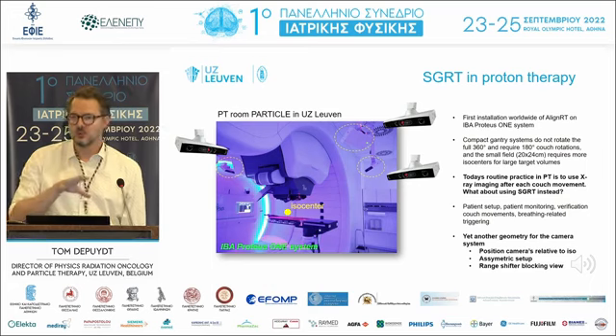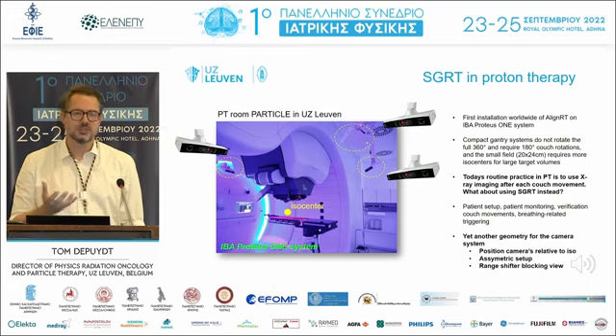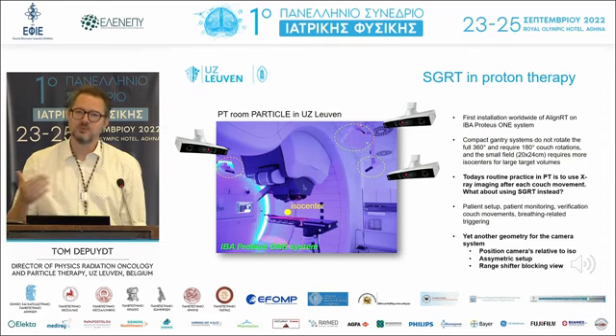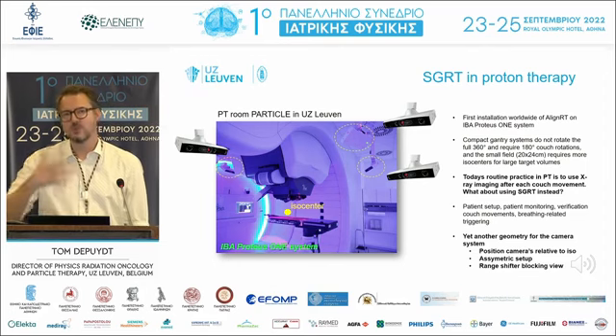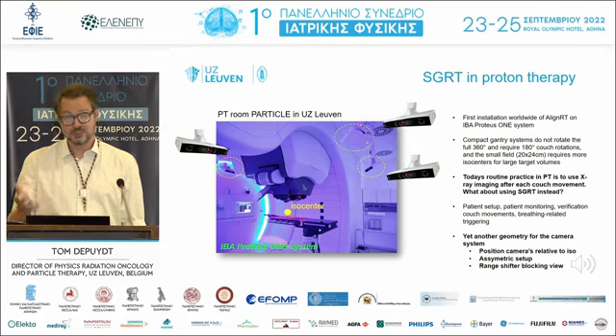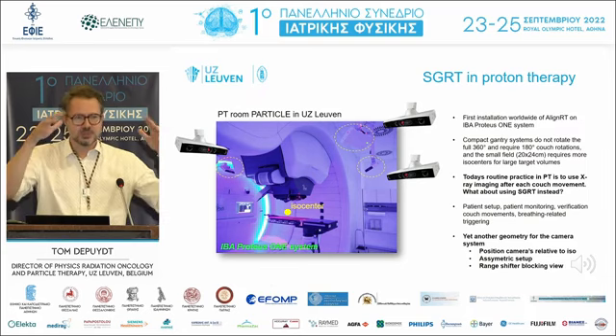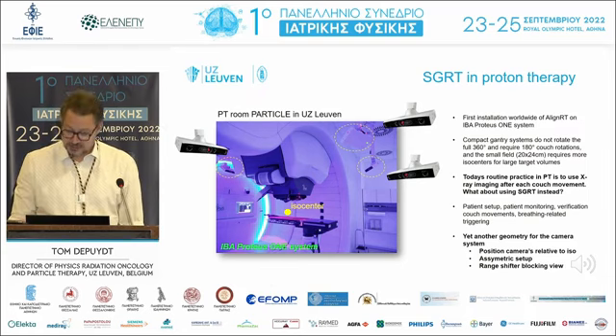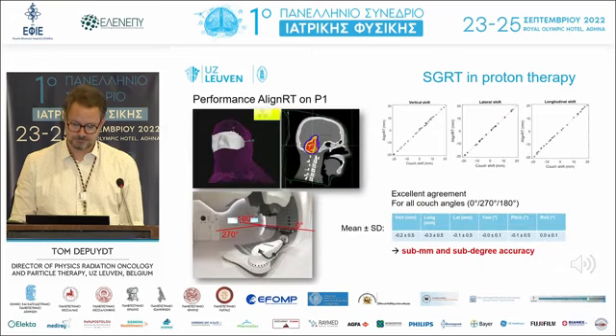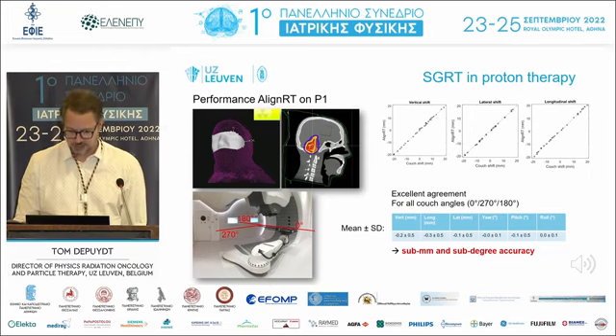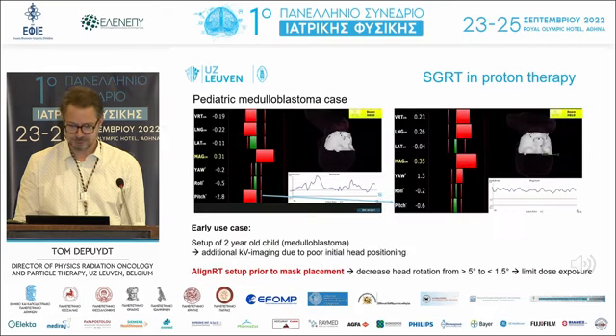And okay, the standard nowadays for imaging is a lot of X-rays. Certainly for pediatrics, we want to go low on the cone-beam CT imaging. So a lot of X-ray imaging, and also because there are very complex movements, couch movements between fields, we always use X-rays to validate that. So the question is, can we use surface scanning for that? But it's yet another geometry. It's an asymmetric setup because of the gantry. And the range shifter, I will go into detail about that, also causes problems. So we validated it with the couch positions and saw that there was a good performance of the AlignRT system because it's a new setup, so we had to validate it. But it showed sub-millimeter and sub-degree accuracy.